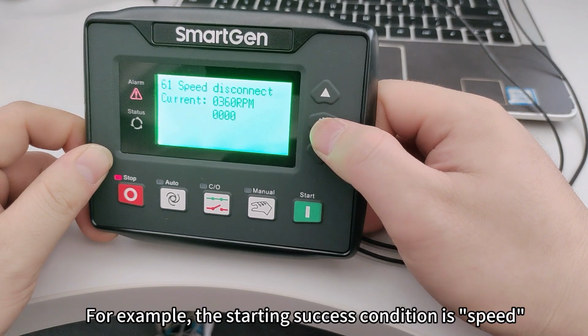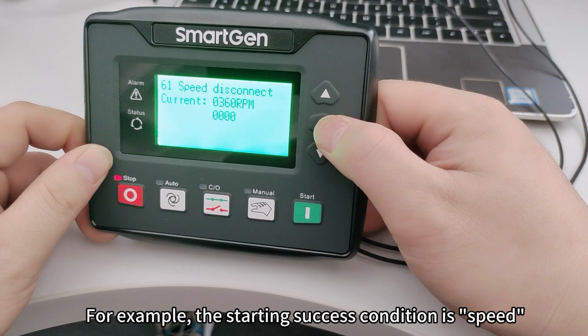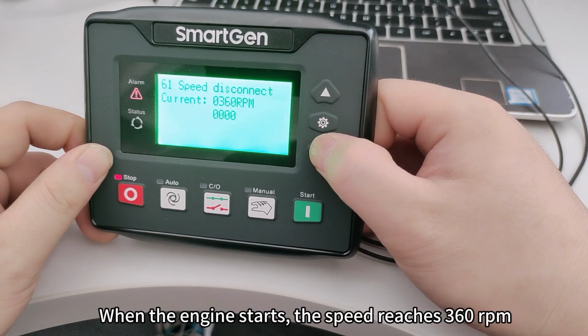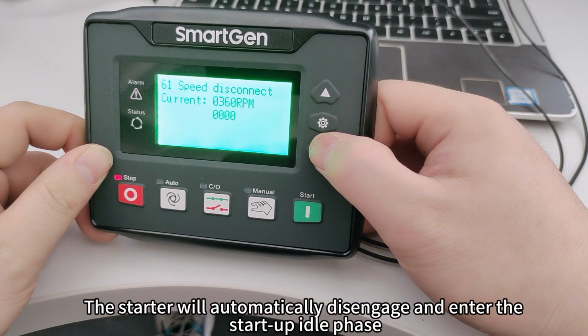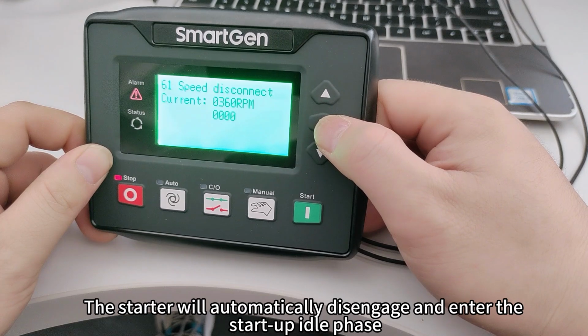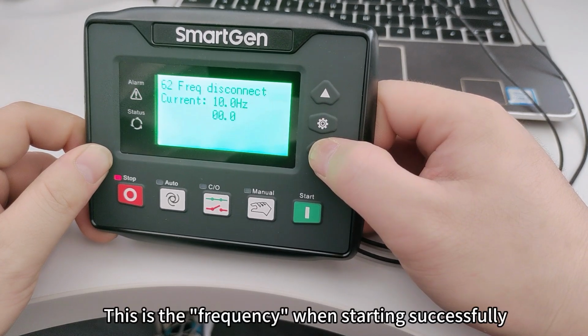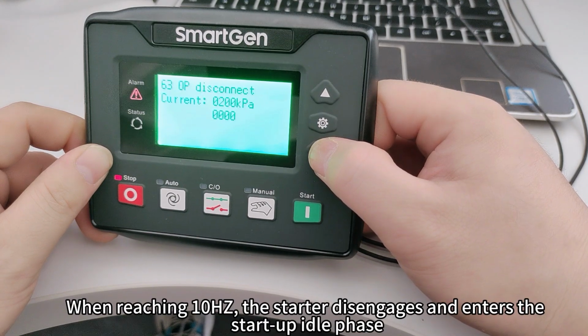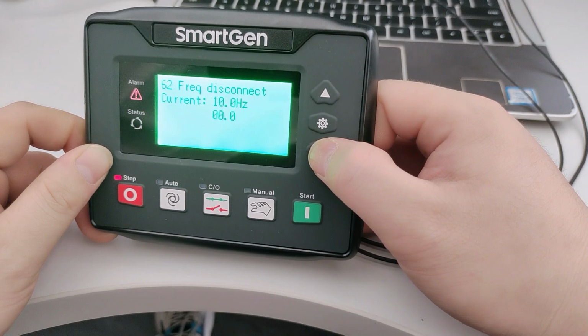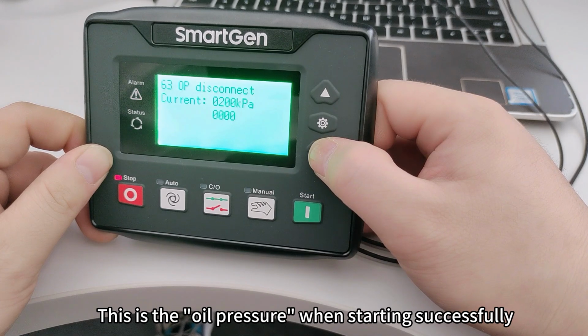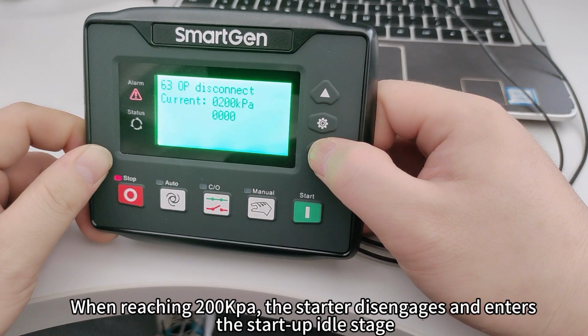For example, the starting success condition is speed. When the engine starts, the speed reaches 360 RPM. The starter will automatically disengage and enter the startup idle phase. This is the frequency when starting successfully. When reaching 10 Hz, the starter disengages and enters the startup idle phase. This is the oil pressure when starting successfully. When reaching 200 kPa, the starter disengages and enters the startup idle stage.